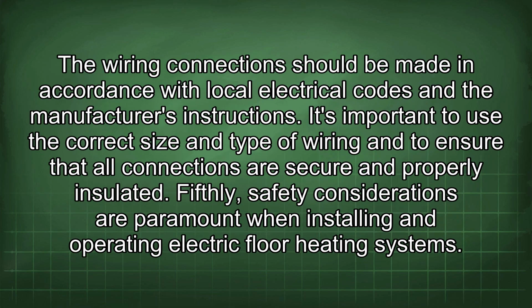The wiring connections should be made in accordance with local electrical codes and the manufacturer's instructions. It's important to use the correct size and type of wiring and to ensure that all connections are secure and properly insulated. Fifthly, safety considerations are paramount when installing and operating electric floor heating systems.